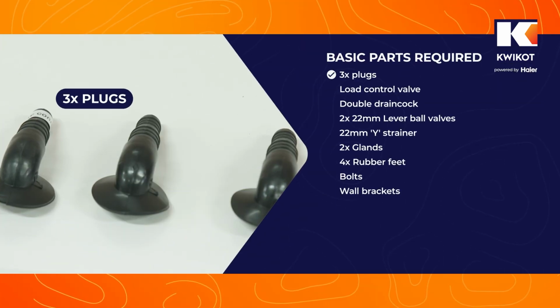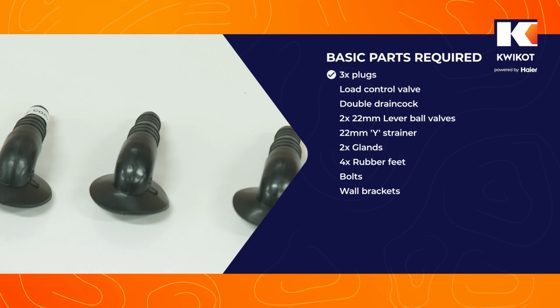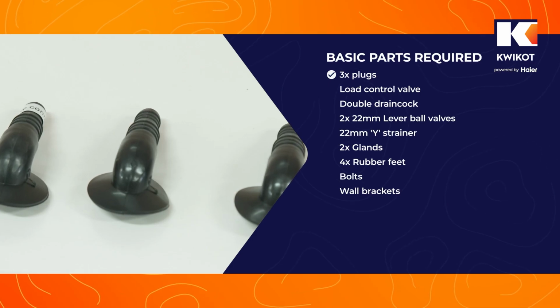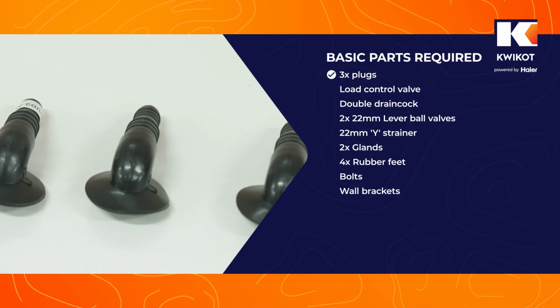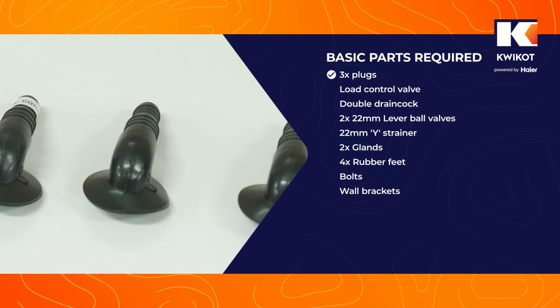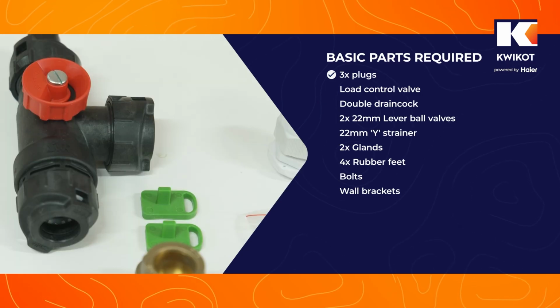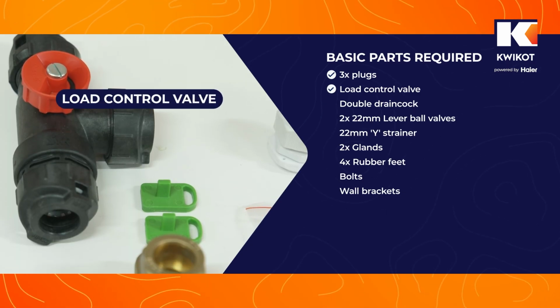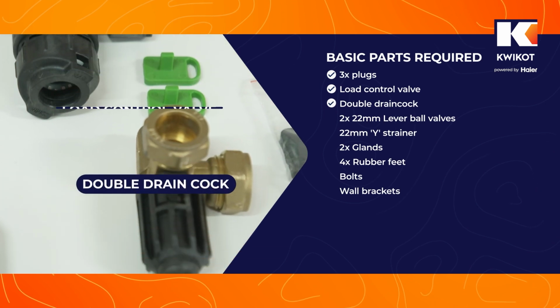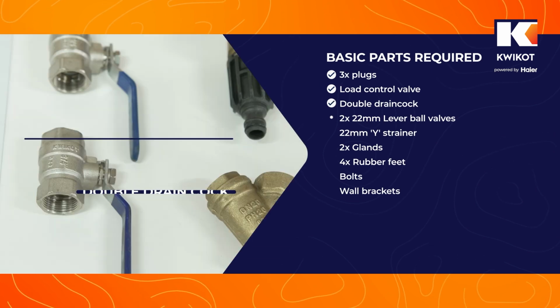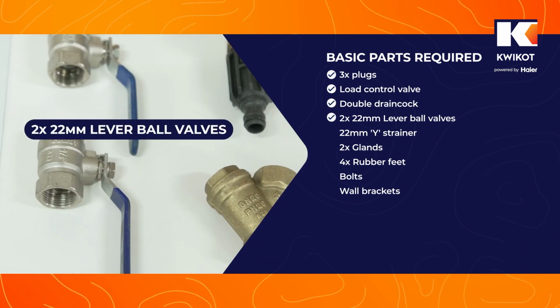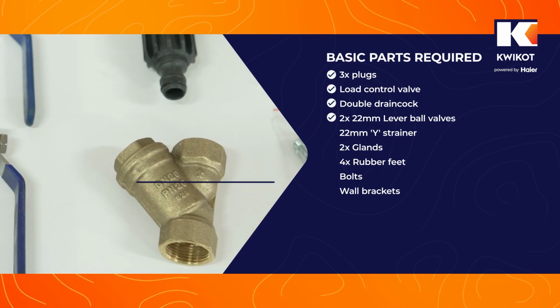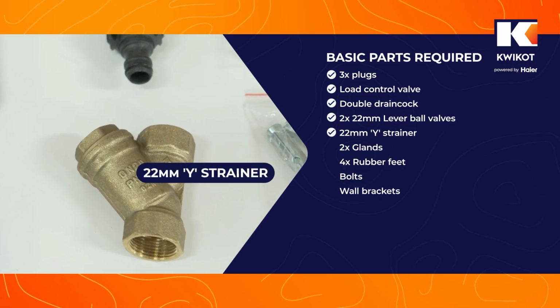These 3 plugs, which are fitted to the condensation outlet points underneath the heat pump for draining purposes, and you can fit a conduit pipe to these if your heat pump is to be installed in a high position. The heat pump kit also includes a load control valve, a double drain cock, 2 lever ball valves, both 22mm in diameter, and a 22mm Y strainer.